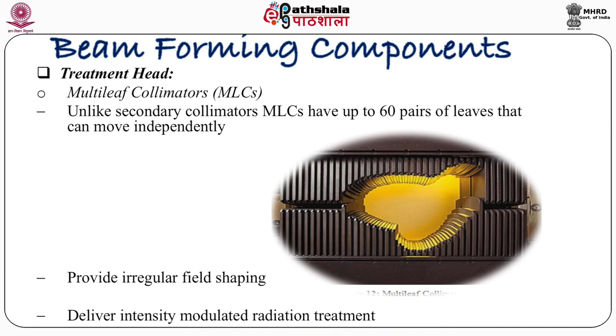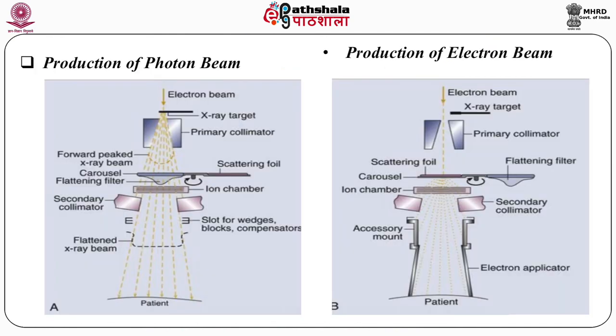The treatment head also contains multi-leaf collimators (MLCs), which is a very advanced feature over the cobalt machine. Unlike secondary collimators, MLCs have up to 60 pairs of leaves that can move independently and provide irregular field shaping. With the help of this, we can modify the intensity of the output of the linac, delivering Intensity Modulated Radiation Treatment (IMRT). This image shows how the electrons are coming out from the linac and falling on the flattening filter or the scattering filter, and then falling on the patient surface. Each and every part is self-defining.